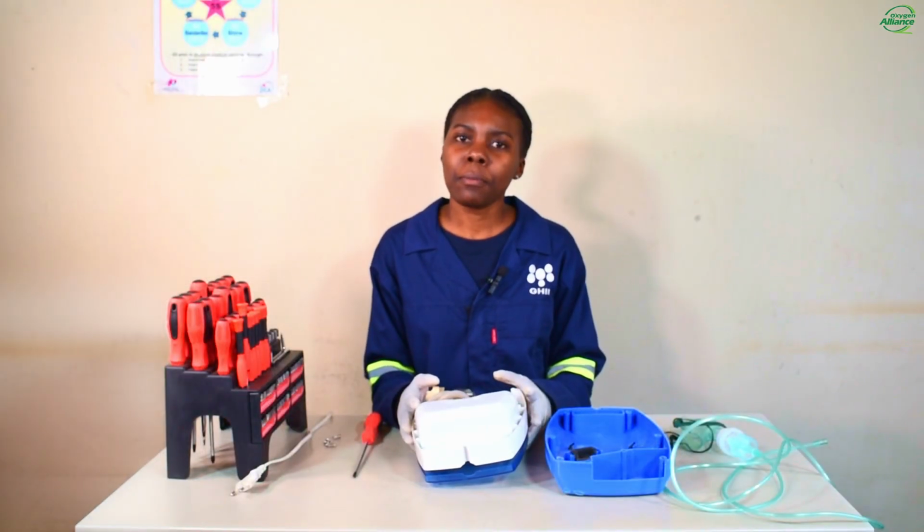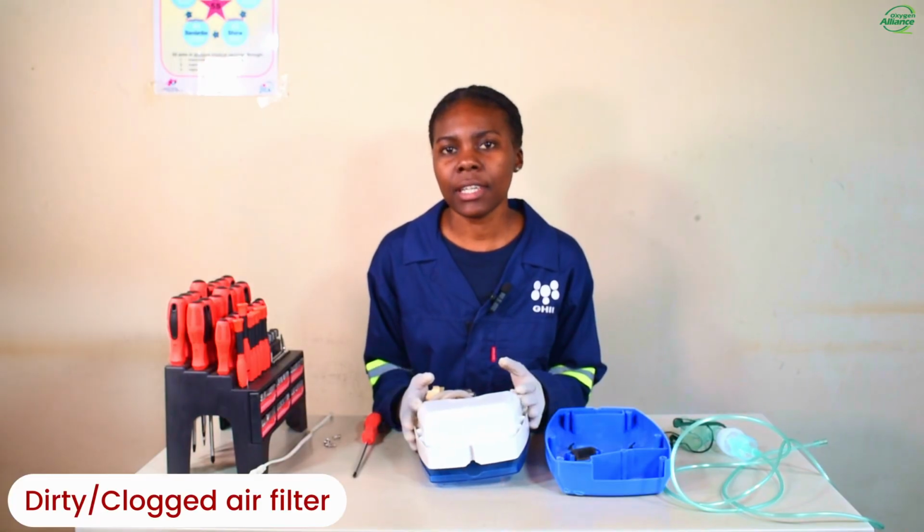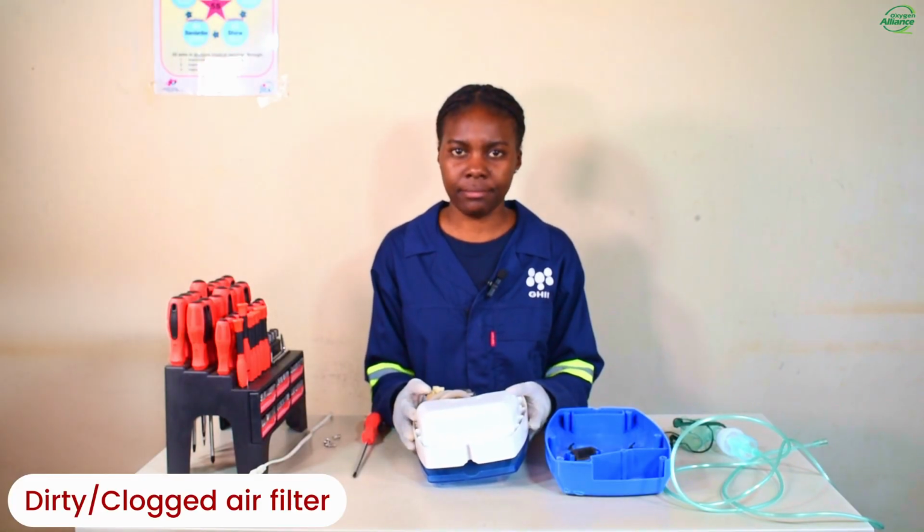If a nebulizer is not producing mist, there are several possible causes. Some are technical, while others are user-related issues. I'll now take you through some of the most common causes of no mist production. The first common cause of no mist production is a dirty or clogged air filter.